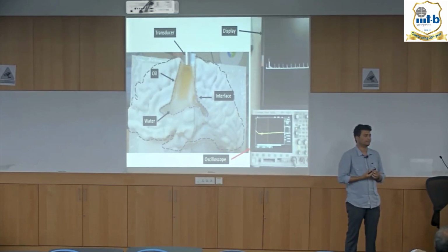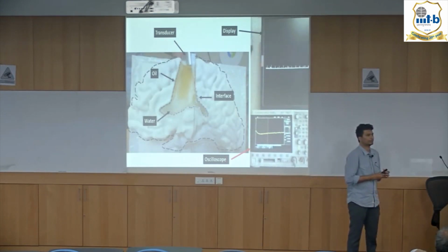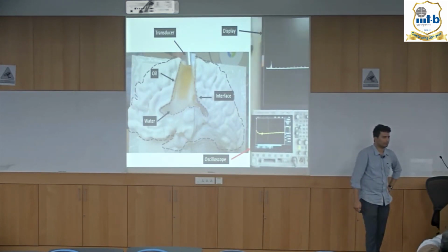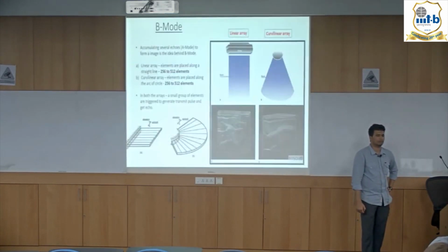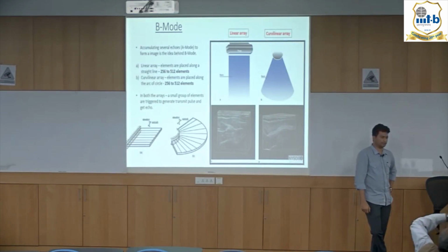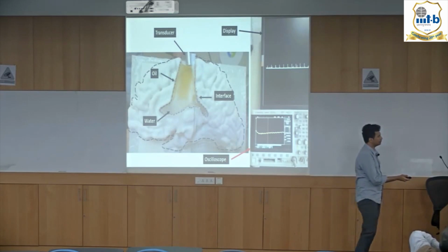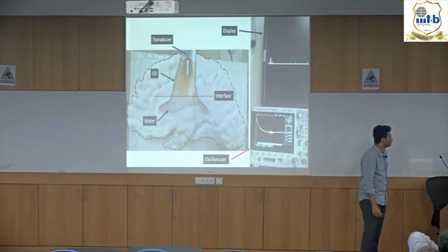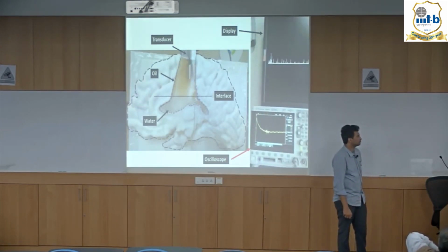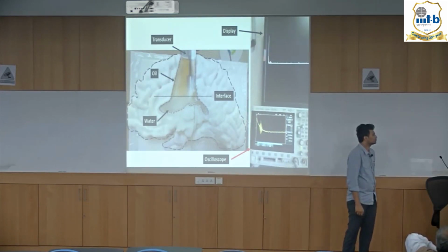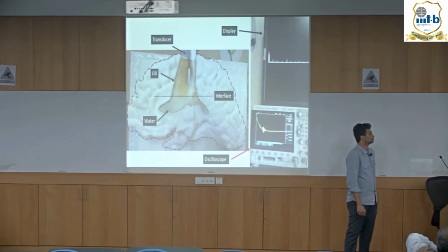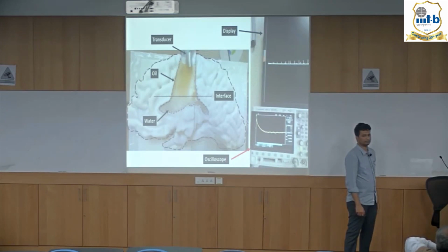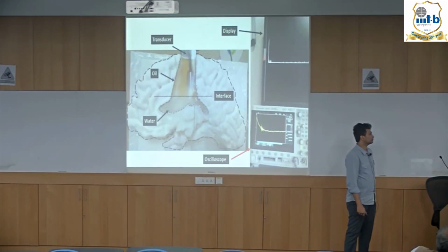One advantage with this is you can afford to have a very low tolerance when you are far away from the target. But as you go closer to the target, your tolerance will become tighter. The surgeon will recognize the echo and immediately know that the ventricle is near. When they are far away, they can say it's 3 millimeter plus or minus 1 millimeter. Then, using this echo, as they guide this in, it can become smaller, 1 millimeter plus or minus 0.1 millimeter.